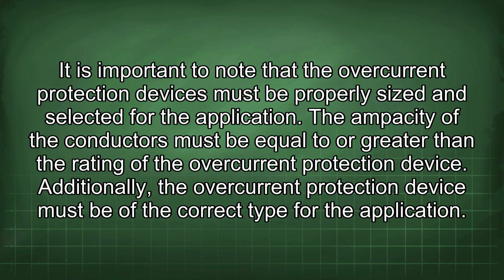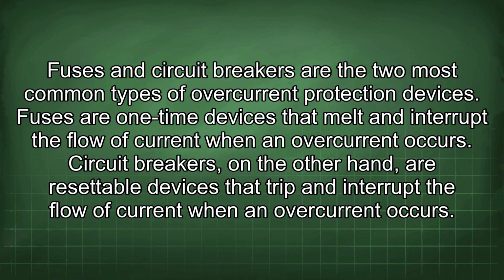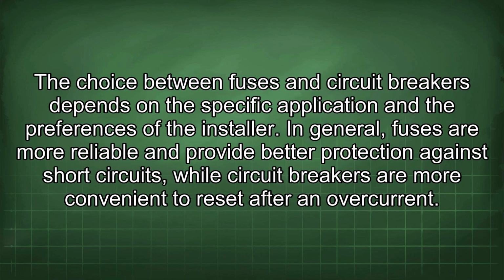It is important to note that the overcurrent protection devices must be properly sized and selected for the application. The ampacity of the conductors must be equal to or greater than the rating of the overcurrent protection device. Additionally, the overcurrent protection device must be of the correct type for the application. Fuses and circuit breakers are the two most common types of overcurrent protection devices. Fuses are one-time devices that melt and interrupt the flow of current when an overcurrent occurs. Circuit breakers, on the other hand, are resettable devices that trip and interrupt the flow of current when an overcurrent occurs. The choice between fuses and circuit breakers depends on the specific application and the preferences of the installer. In general, fuses are more reliable and provide better protection against short circuits, while circuit breakers are more convenient to reset after an overcurrent.